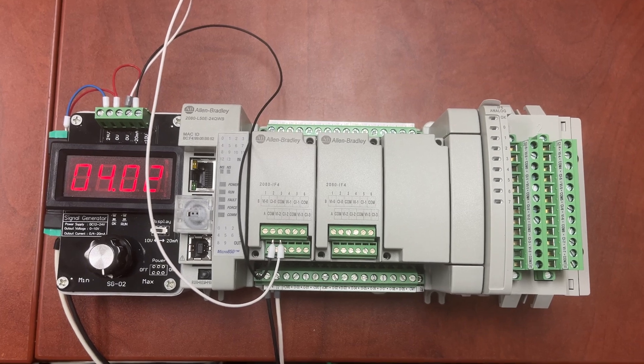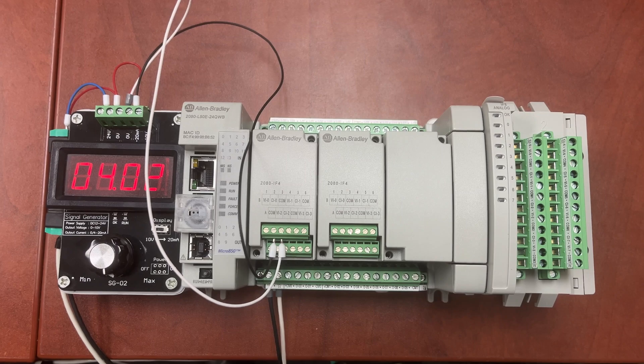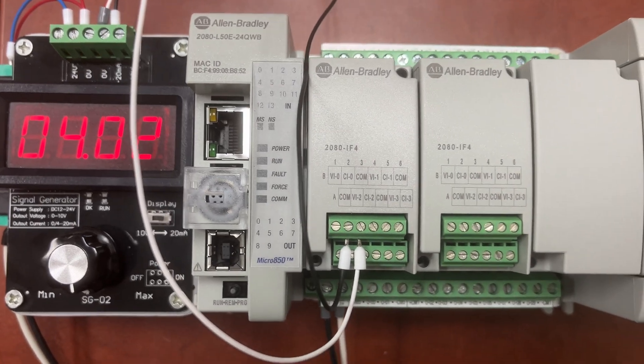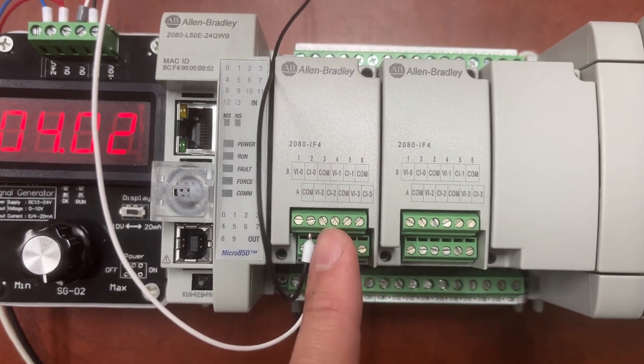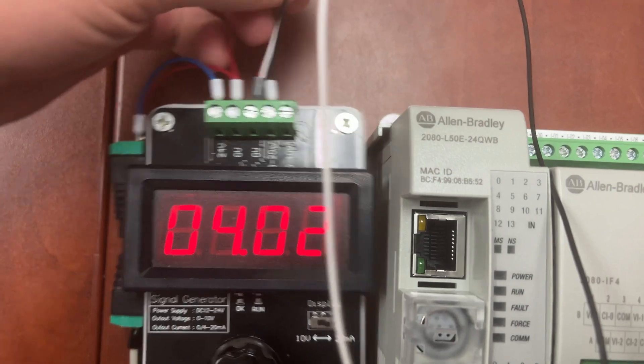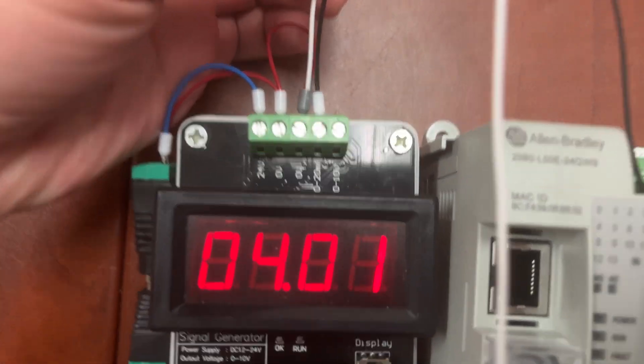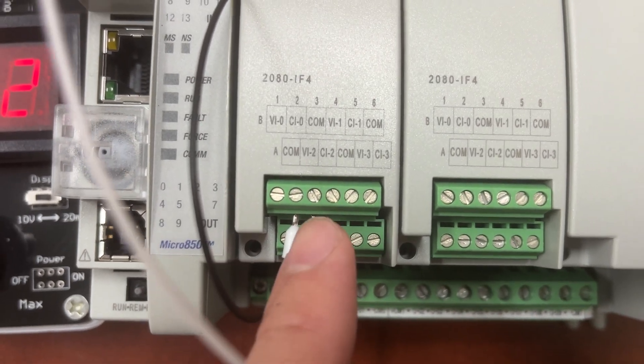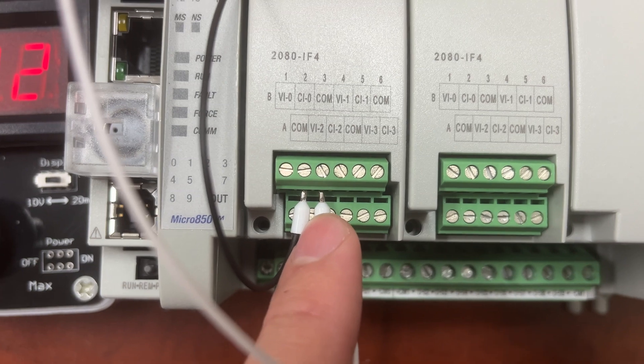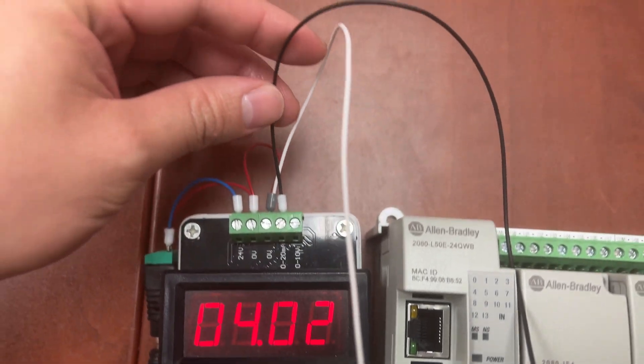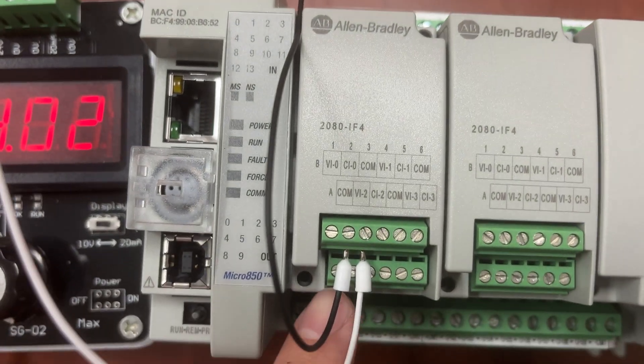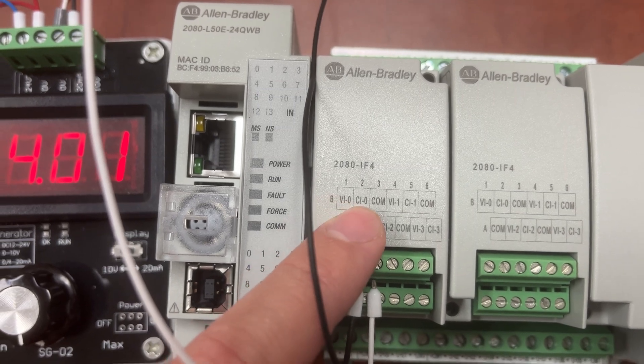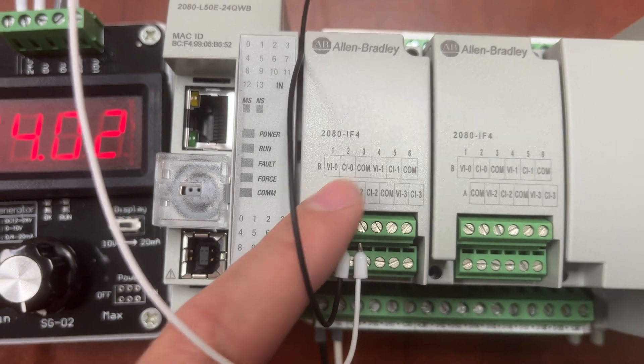If we have a 4 to 20 milliamp signal from a transmitter, this is how it should be wired to the PLC or a plugin module. We have the white wire for zero-volt wire to COM and we have a black wire to CI zero, current input channel zero.